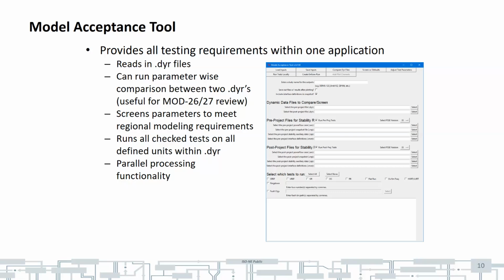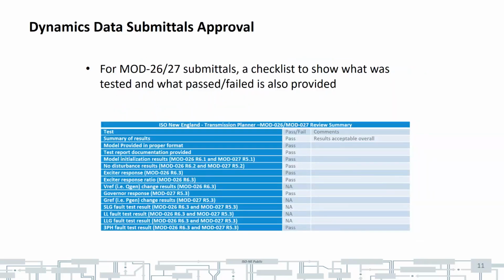Let's go to the next slide. This gives an indication of the number of tests that are performed and what the test is relevant to and what it's testing for. We do this when we are accepting models from as-built generators seeking to go commercial, checking that the model's in proper format, test report documentation was provided, that it initializes, and that it goes through stable performance when there's no disturbance. We look at the exciter response, the governor response, and we run some tests: single line to ground, line to line to ground, line to line, and three-phase faults. To be accepted before a generator can go commercial, the model and data information must at least pass these tests.